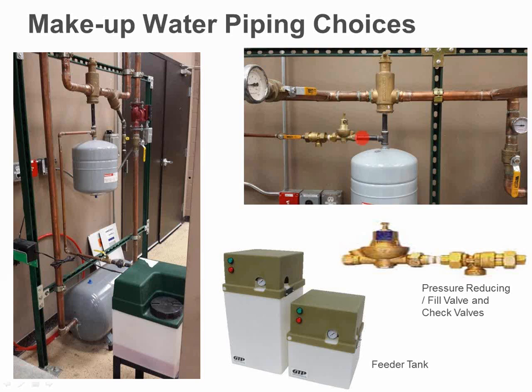And the nice thing with the feeder tank, it will tell you when you do have a leak, because the water level in the tank will go down, or the glycol. So it does help you in that way, but it also helps you get rid of that $200 fee that some of these villages are trying to impose on people as they're out grabbing money.